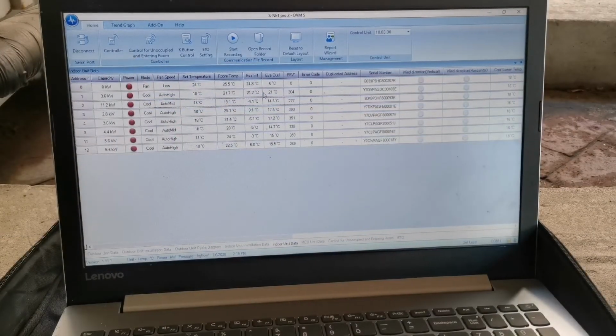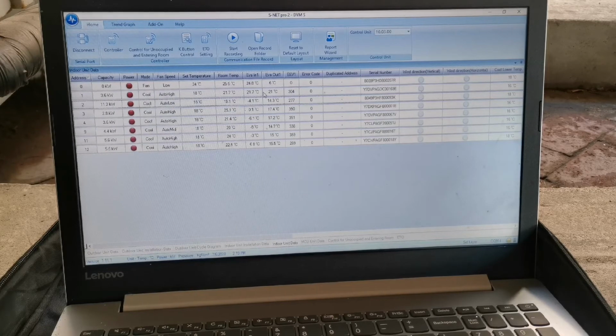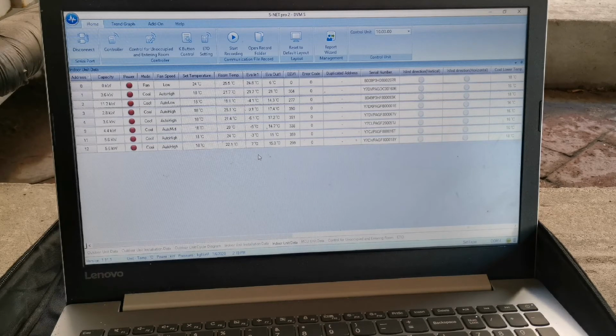Okay guys, so this is very interesting. So we went ahead and switched the system on cooling. The top system over here, which is address number 0, that one was giving us issues. Now we've got that system on fan mode only at the moment. Now if you have a look at the room temperature right on top, it's at 25.3 degrees. Our evaporator in temperature is 24.7. But the interesting thing is the evaporator out temperature is on 9 degrees. So that's a very interesting result that we have so far.